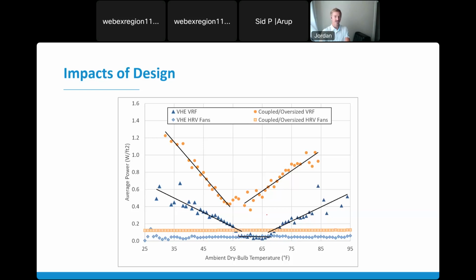They don't continue to run. It's almost nothing. It's less than the ERV fan energy. This coupled oversized system uses a ton of energy, even on very mild days. The reason I'm comparing these buildings is that they are right next to each other, same occupancy type, in the same place, very, very similar buildings, and also almost exactly the same equipment, same efficiency, high efficiency equipment in both situations, but basically 3 times the energy use from not following a couple of the key design requirements, or design principles rather.